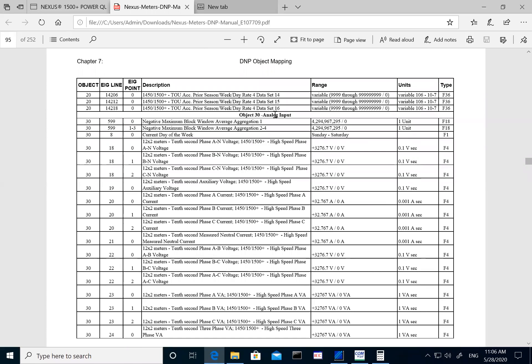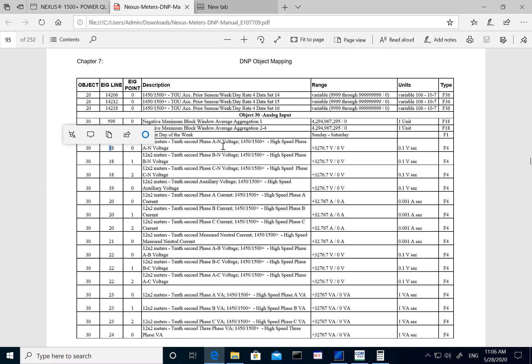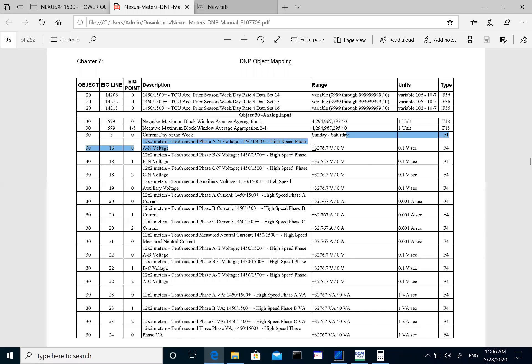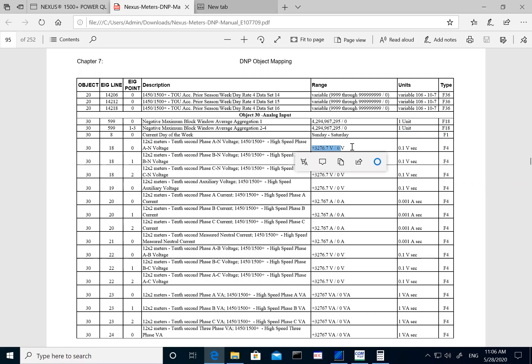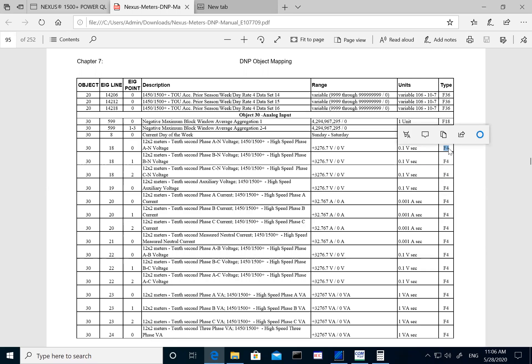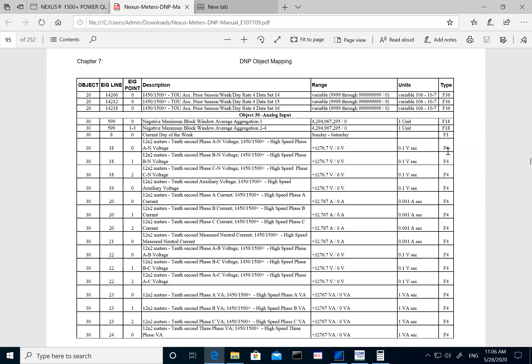This is object 30 analog input, and it shows the object 30 line and point items. Taking the first object point — voltage A to neutral — it shows me the range starts from 0 to 32,767 and has units of 0.1 volts secondary. We also show the data type, which is F4. This data type is important because when I read these registers from the DNP, I would have to do some calculation in my DNP software or DNP RTU to convert it to the actual reading.